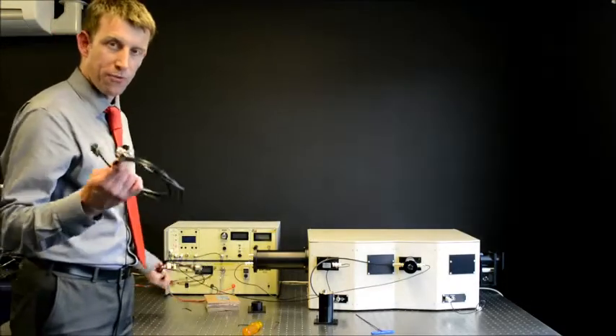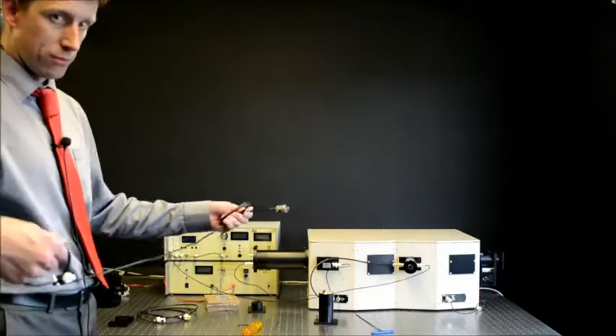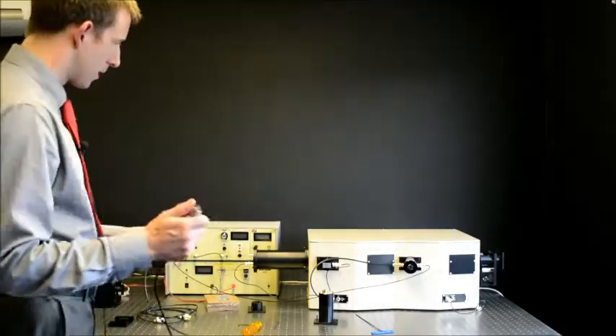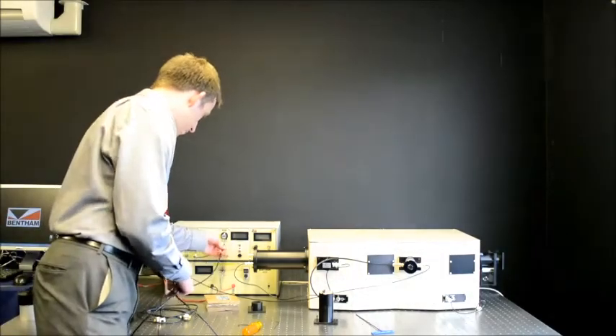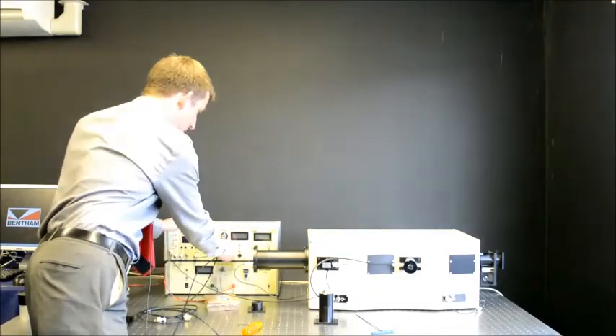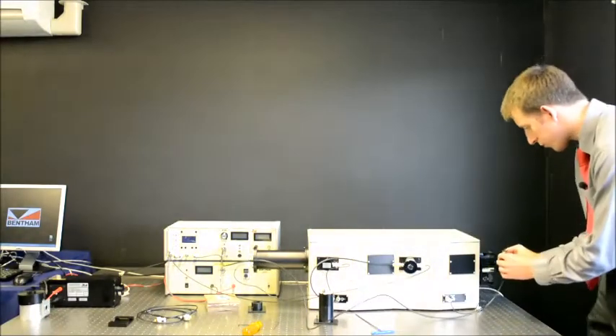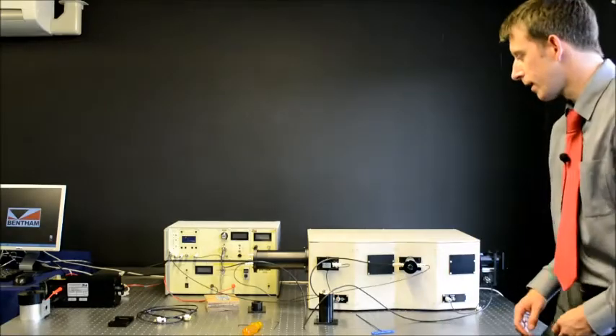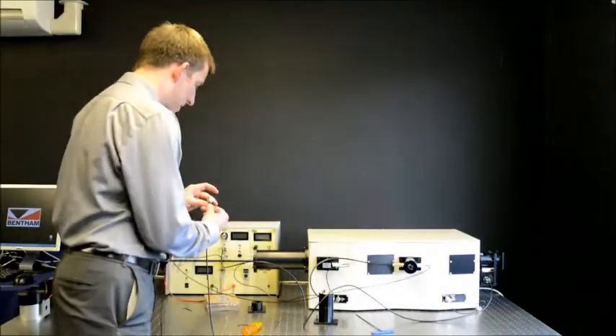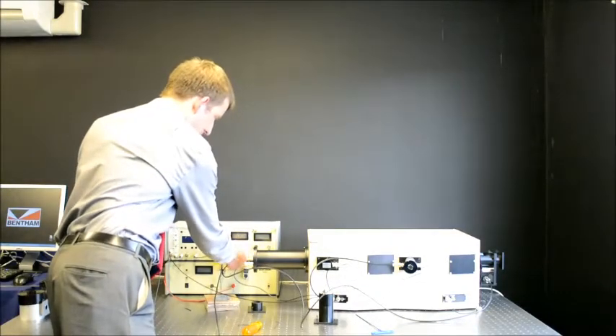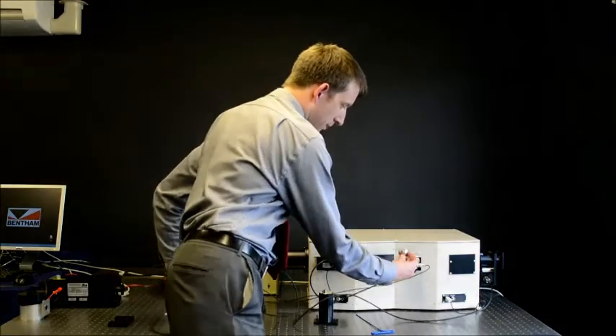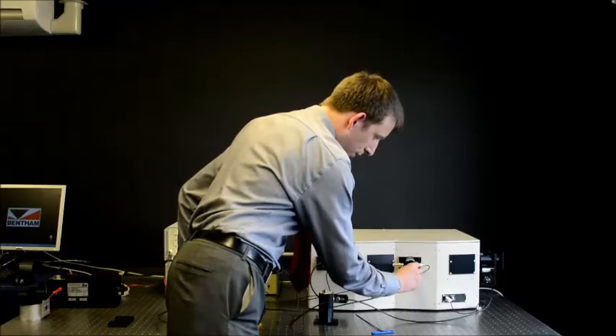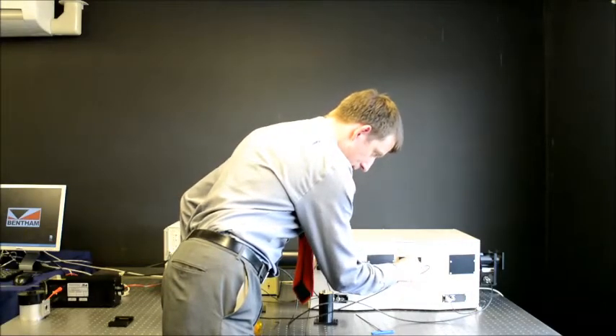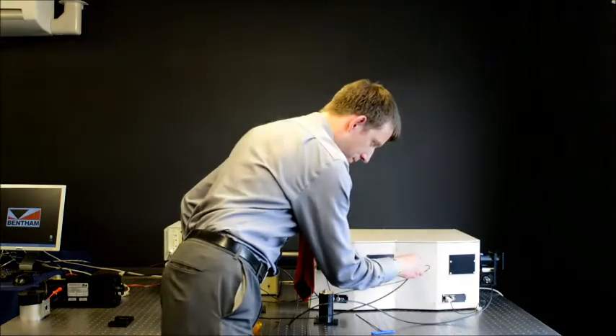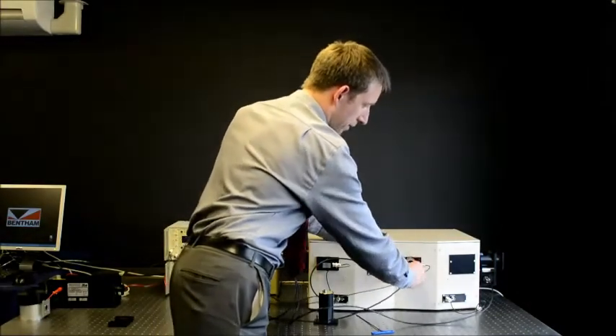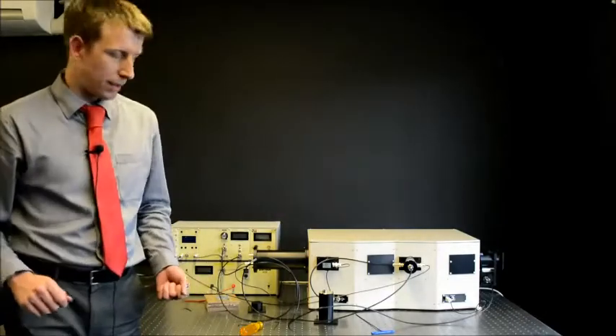We have 2 similar 5-pin cables. We must be careful not to confuse the 2 connections. The first is a 5-pin connection from the 218 module, the optical chopper controller, and that should be connected to the optical chopper. The second connects the CPS1 detector cooler unit to the rear port of the detector for the purposes of cooling. Cooling infrared detectors improves their performance. This detector has a Peltier-based cooling system. Note that these 5-pin connectors have a specific orientation and a collar locks the connector in place.